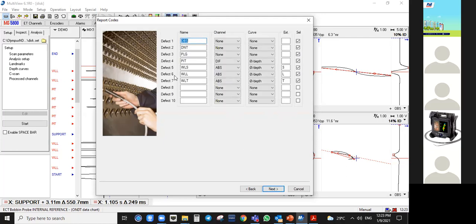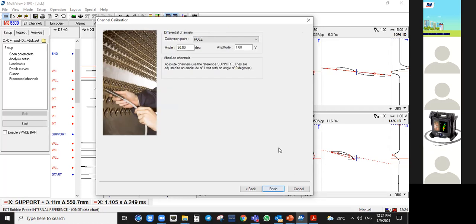These are the defects that you usually see on your inspection. You have your wall loss short, where the extension is S. You have wall loss long, L, and then wall loss tapered, where the extension is T. Select all of these, press next, and then for the RFT standard, the angle for the hole is 90 degrees and the amplitude is 1 volt. For ECT, remember the angle is 40 degrees and the amplitude is 1 volt. For RFT, it should be 90 degrees for the hole. Then just press finish.